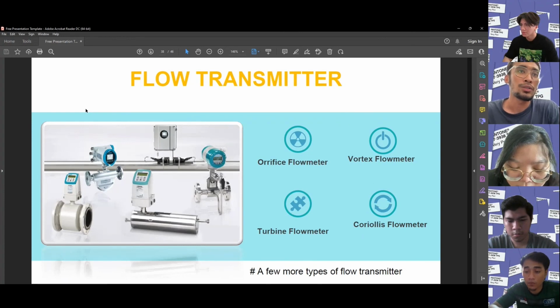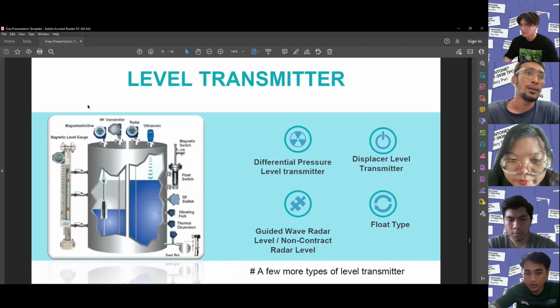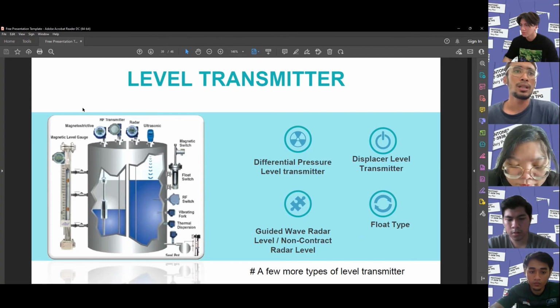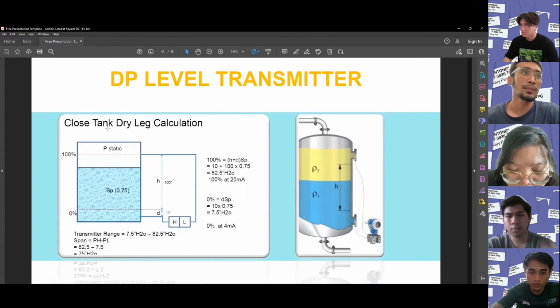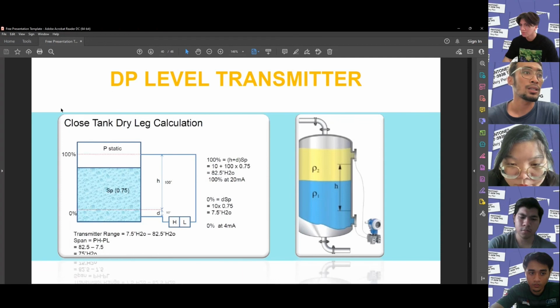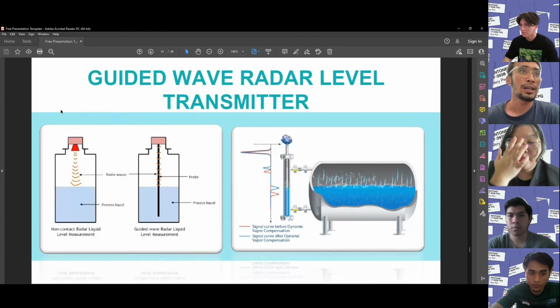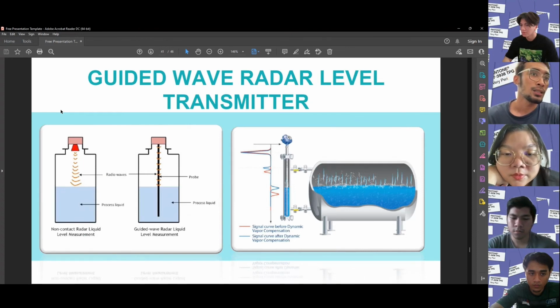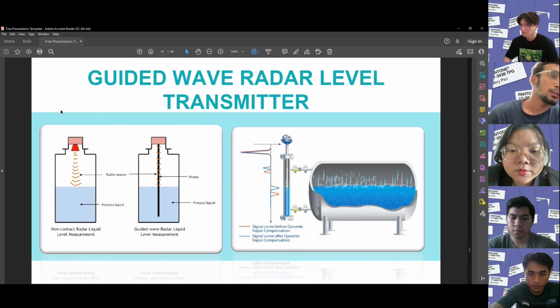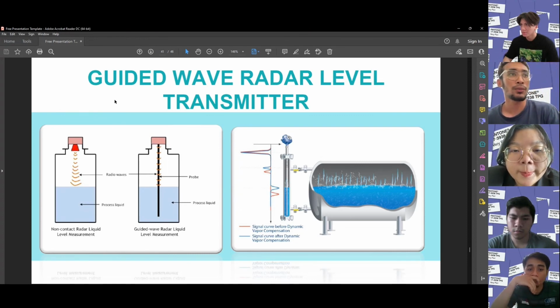For the flow transmitter, there are orifice flow meter, vortex flow meter, turbine flow meter, and Coriolis flow meter. For the level transmitter, it has 4 also, which are differential pressure level transmitter, displacer level transmitter, guided wave radar level or non-contact radar level, and float type. For the DP level transmitter, we can see this is the closed tank dry leg calculation. Next. Guided wave radar level transmitter. This is the diagram for the guided wave radar level transmitter.